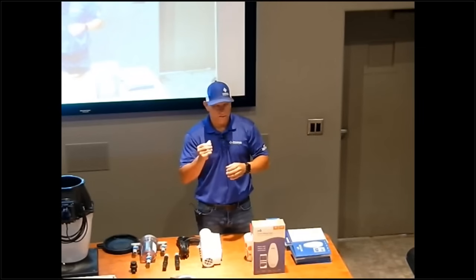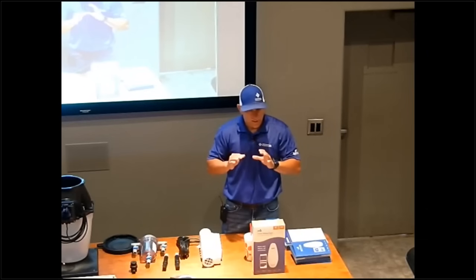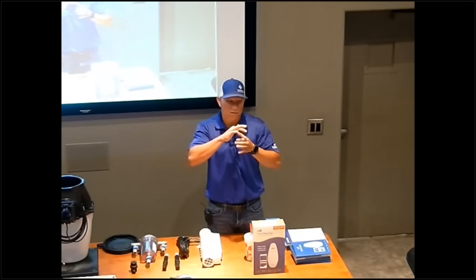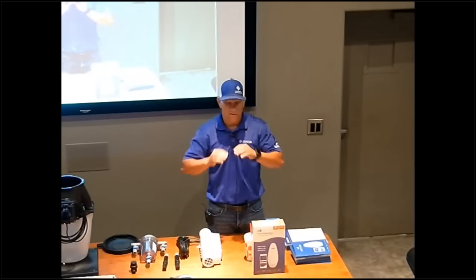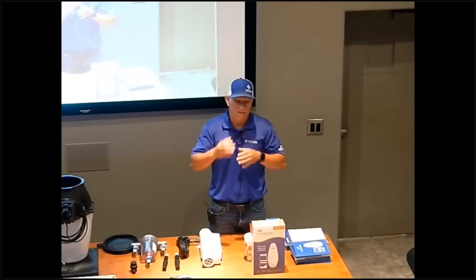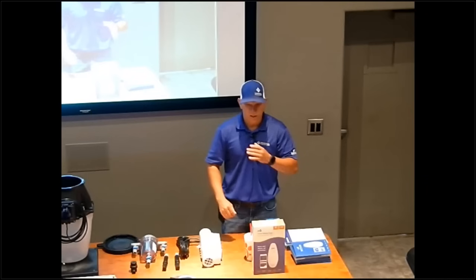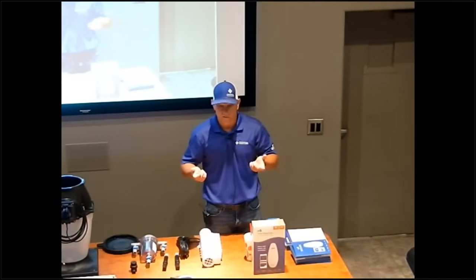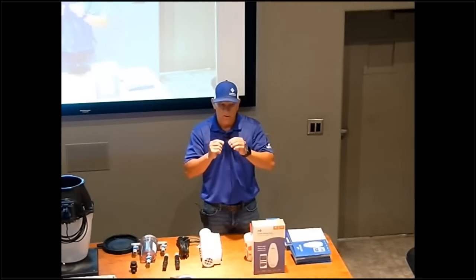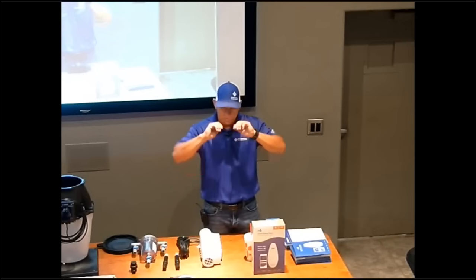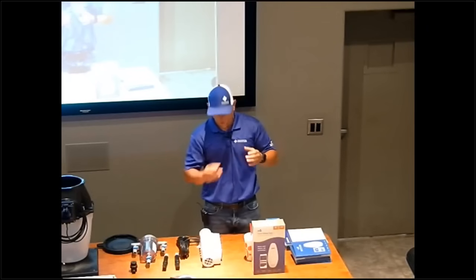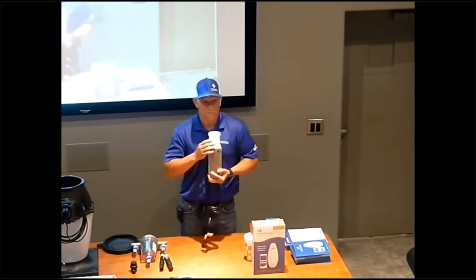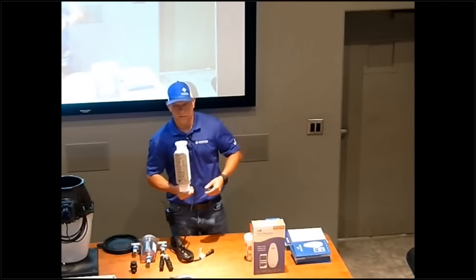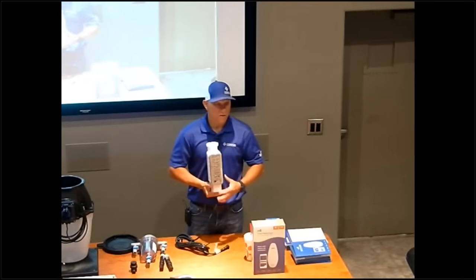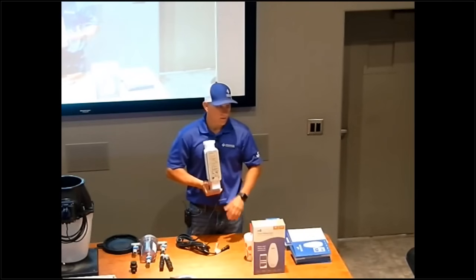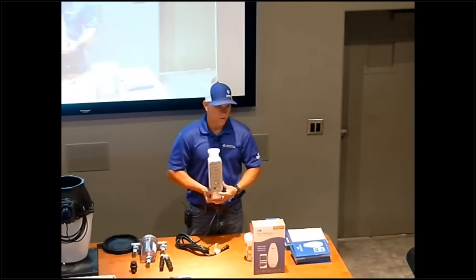I see a lot of people using lube on them. It's okay, but you're not trying to fix a leak with it, you're just conditioning the O-ring. So just a very small amount - some people think the more you put on, the more it's going to seal, but it actually doesn't allow it to seal. You're better off using a dry O-ring than a too-lubed O-ring. So pop it off, clean it up real good, a little tiny bit of lube just to condition it, flip it around, and put it back on top and bottom. The only thing you want to make sure is there's a flow arrow on the cell - make sure it's in the correct orientation. If it's your first time cleaning the cell, find out if the arrow is pointing down or up, and make sure when you put it back it's in the same orientation.